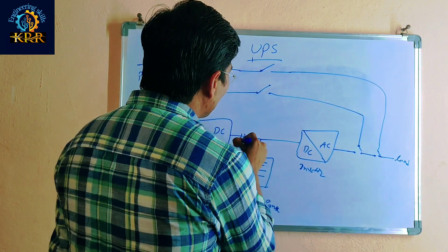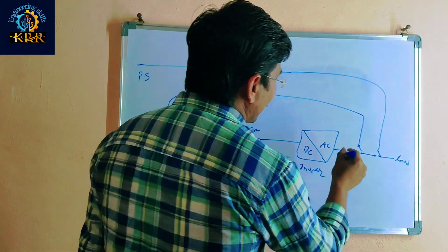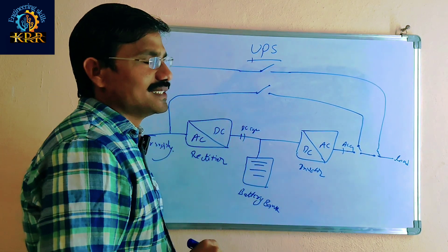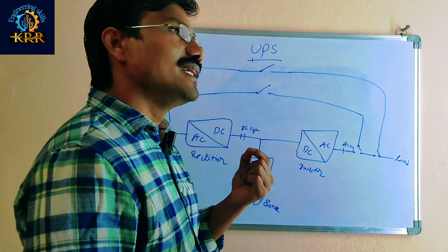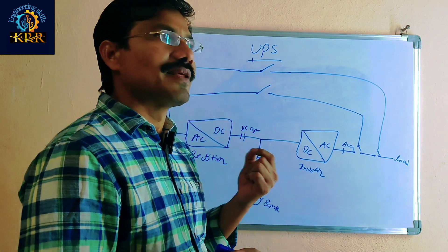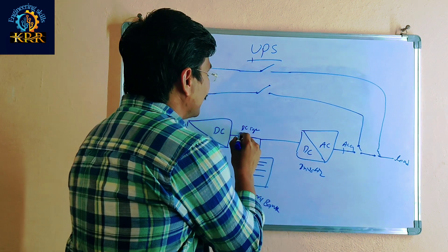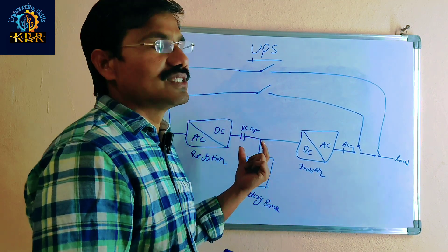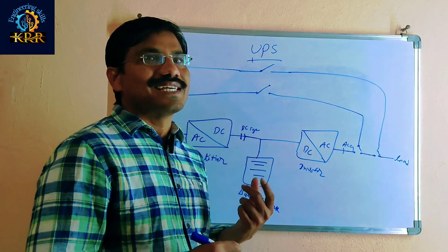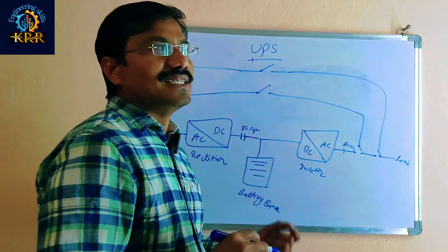After that, here some DC capacitors are there. The DC coming out of the rectifier is not pure DC — some ripple AC is available. Those DC capacitors block the ripple AC so that pure DC only passes through. The DC capacitors work like a filter; they block the AC ripple.